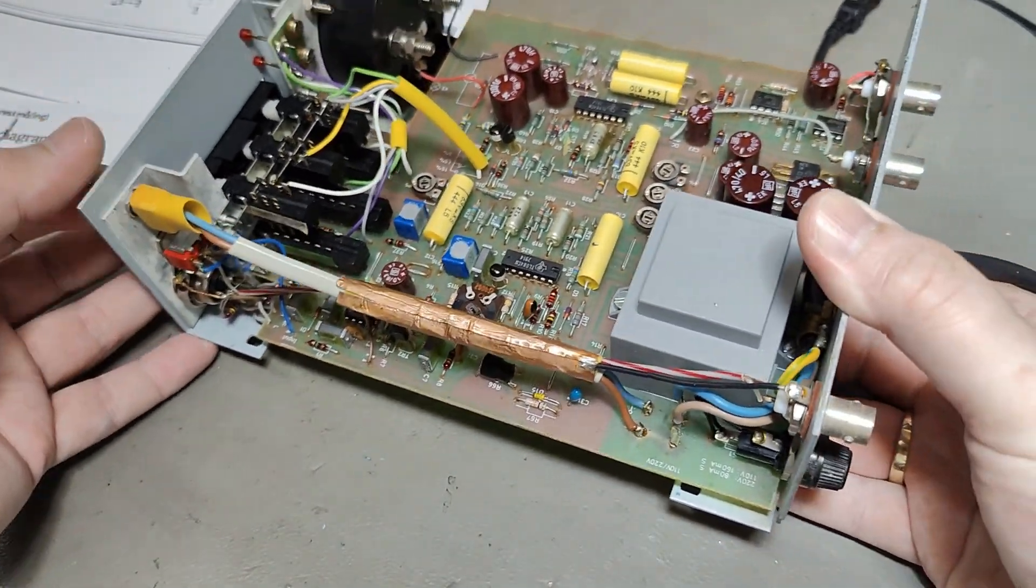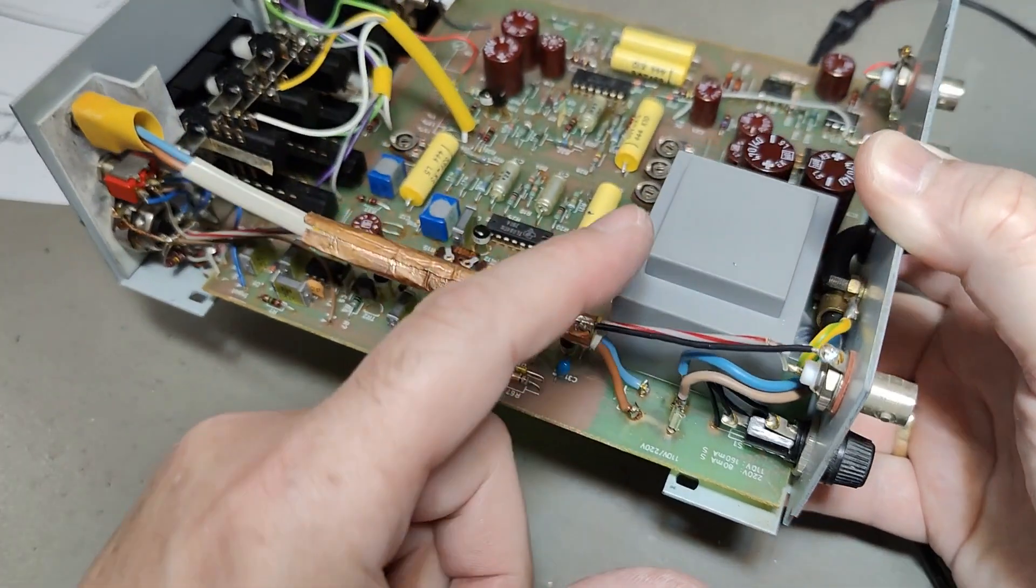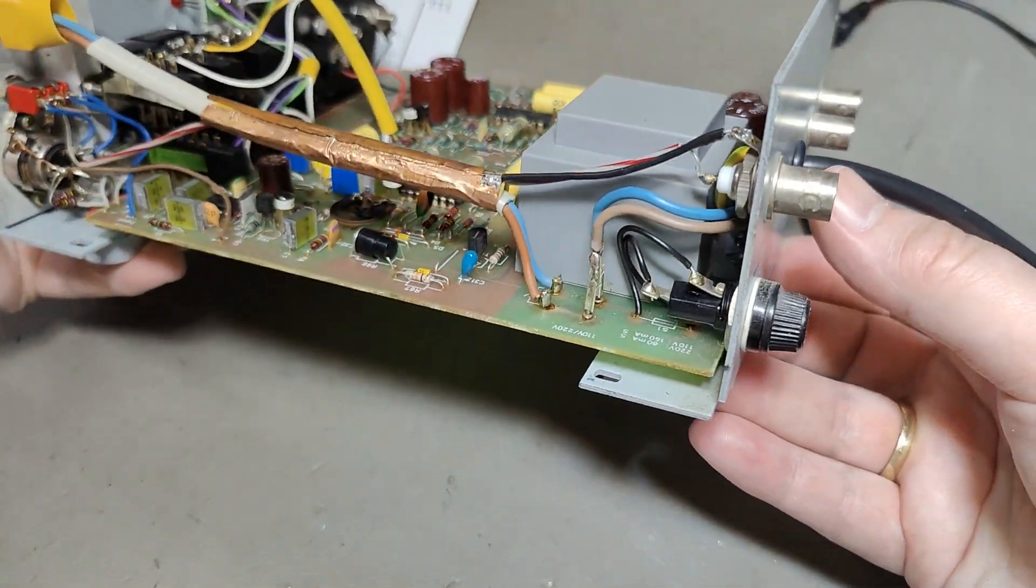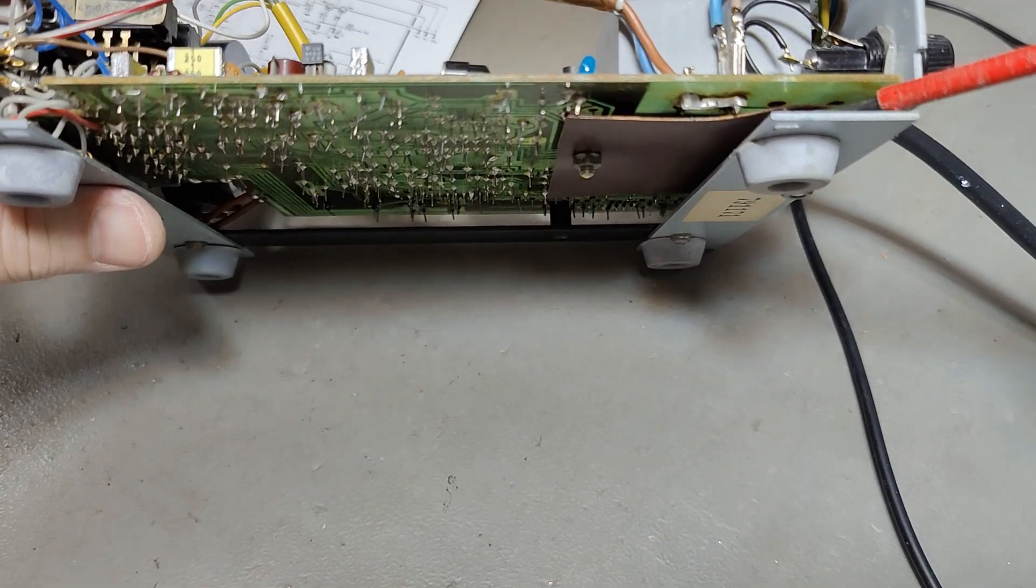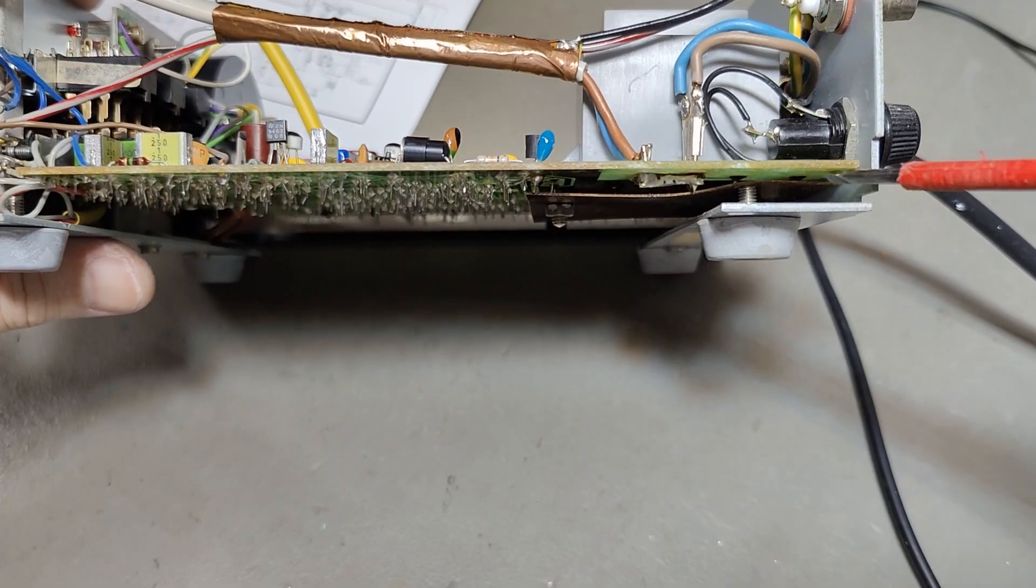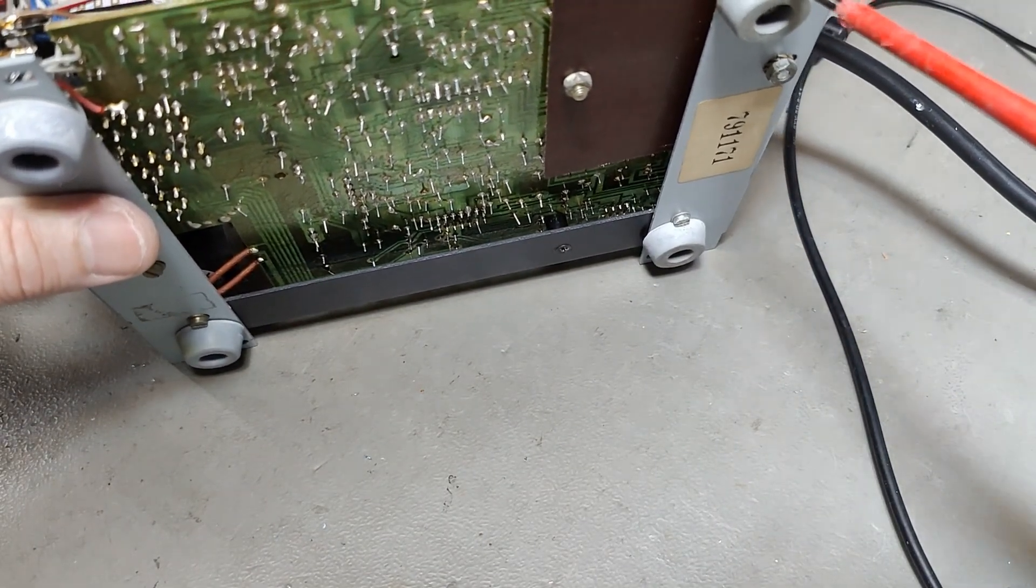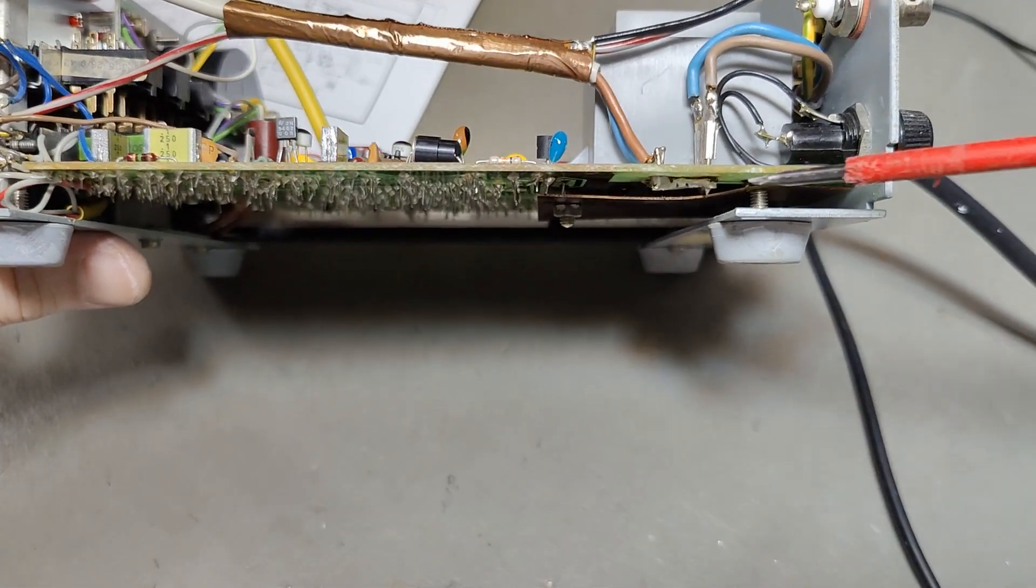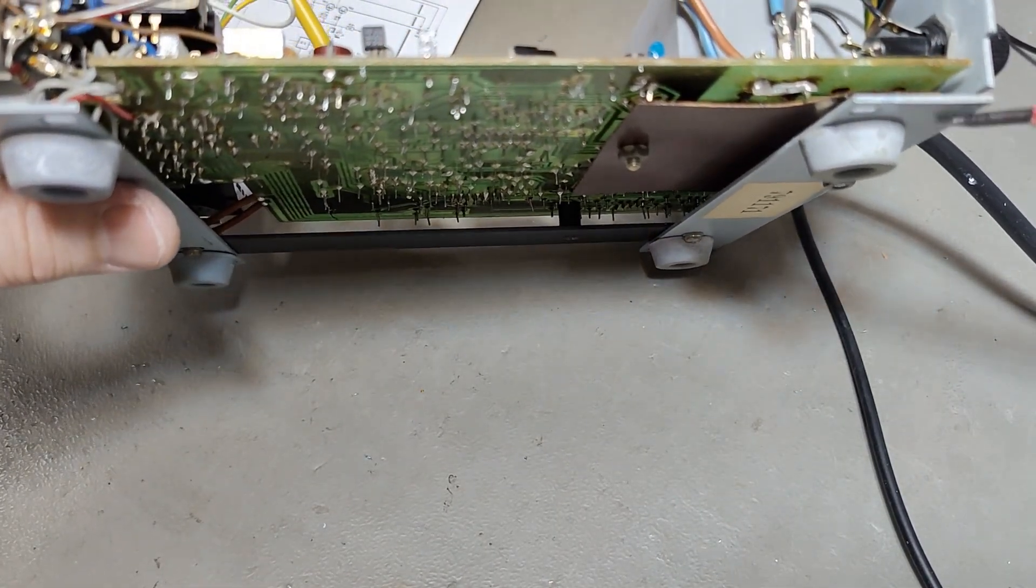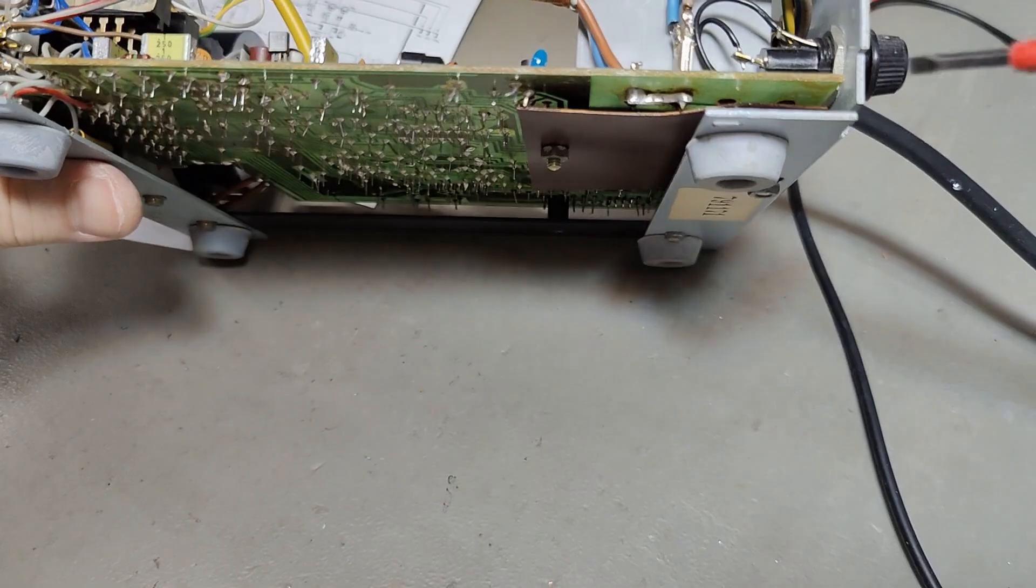And also, there's another little design problem. If you see the screw here, see the length of that screw that goes, I mean, this is a thin isolation material. But when this plastic rubber stuff goes into, I don't know what it goes into. You need to tighten the screw a little bit more and more, right? And then you can imagine the screw will eventually break through this. And then you have chassis directly connected to mains. This is the mains fuse. Genius placement of that screw. They should of course have used shorter screws.